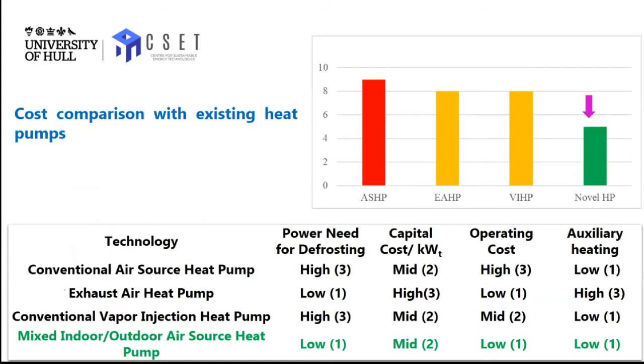So this is a general comparison between our technology and existing heat pumps, including the conventional air source heat pump, exhaust air heat pump, and conventional vapor injection heat pump. In terms of power demand for defrosting, our technology has the lowest power demand because we almost have no need for power for defrosting. We use ventilation energy.